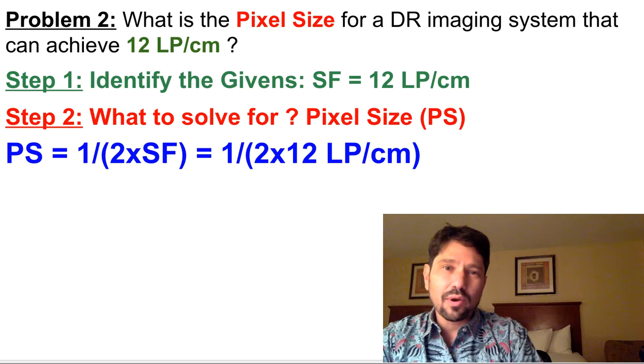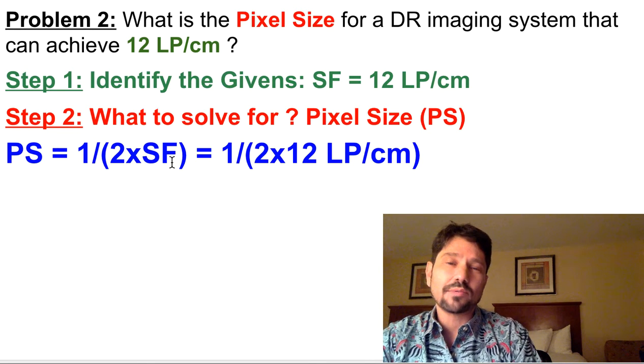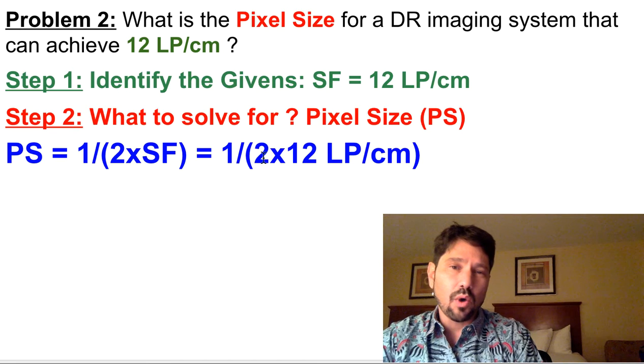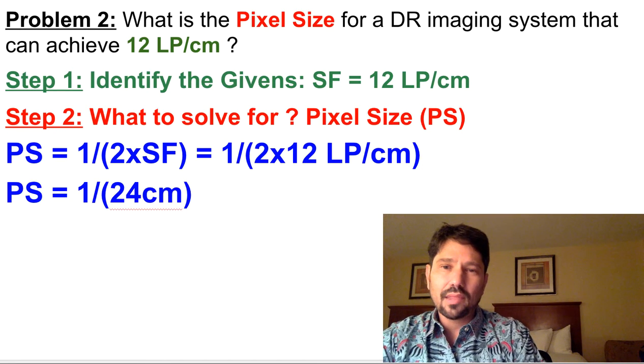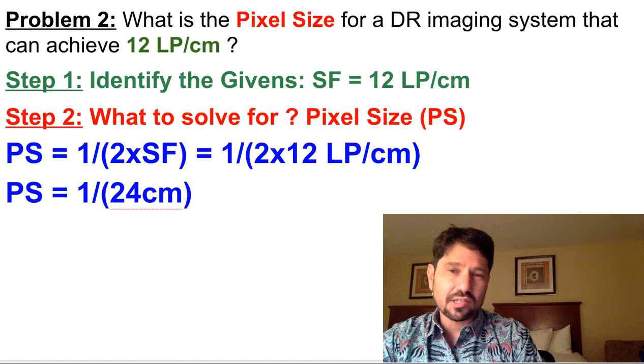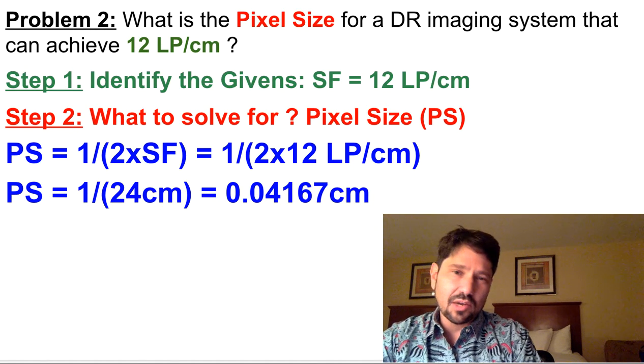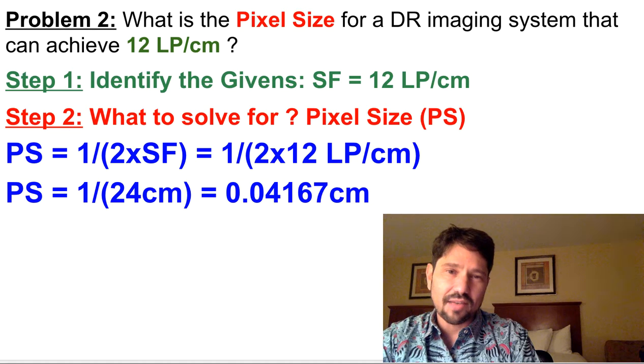All right, so back to our problem. We're going to be solving for pixel size. Pixel size equals 1 over 2 times spatial frequency, or 1 over 2 times 12 line pairs per centimeter, which equals 1 over 24 centimeters, which equals 0.04167 centimeters.